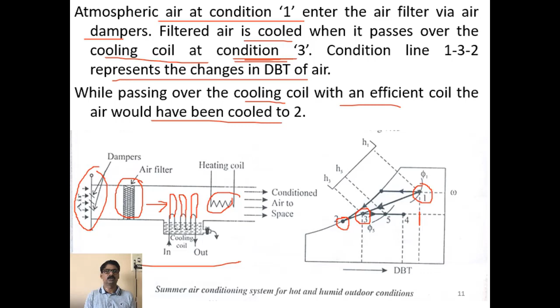Now while passing over the cooling coil with an efficient coil, air would have been cooled to 2. So that is what I told you. Efficient cooling will result in condition 2, but inefficiency of the cooling coil results in condition at 3. As the air temperature is still below the required comfort condition, now it is passed over the heating coil. You see why it is passed over the cooling coil here in the beginning, mainly to remove the moisture.